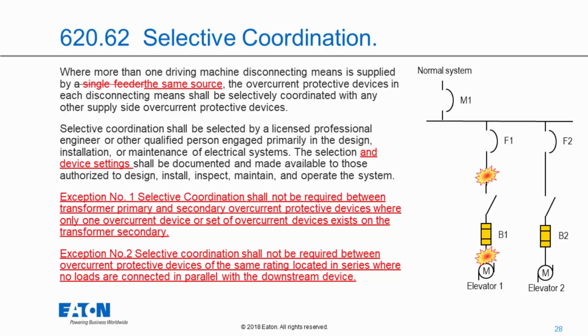One of the first sections where we have a requirement for selective coordination is with multiple elevators. And the change here was they changed where it talks about where more than one driving machine disconnecting means is supplied by a single feeder. They changed that to the same source. And then it goes on to state that the overcurrent protective devices in each disconnecting means shall be selectively coordinated with any other supply side overcurrent devices.